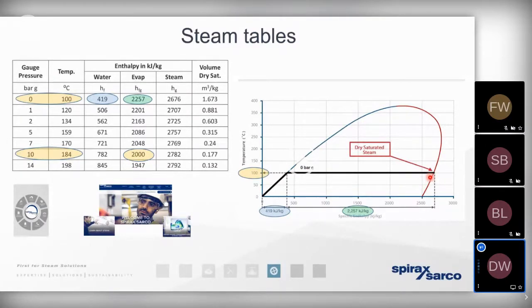So if we're not on top of how we're generating steam in the boiler house, for example, if we've got less than optimum boiler controls, if we've got fuel that's slightly contaminated, it's highly likely that we won't be putting the full latent heat energy into that boiling water. In other words, the steam will exist slightly to the left of what we call the dry saturated steam line. So that word dry saturated is critically important. Dry, well, it means there's no moisture entrained within it. Saturated, it means it's saturated with energy. Cannot contain any more energy than 2,676 kilojoules in the example of generating steam at 0 bar gauge.